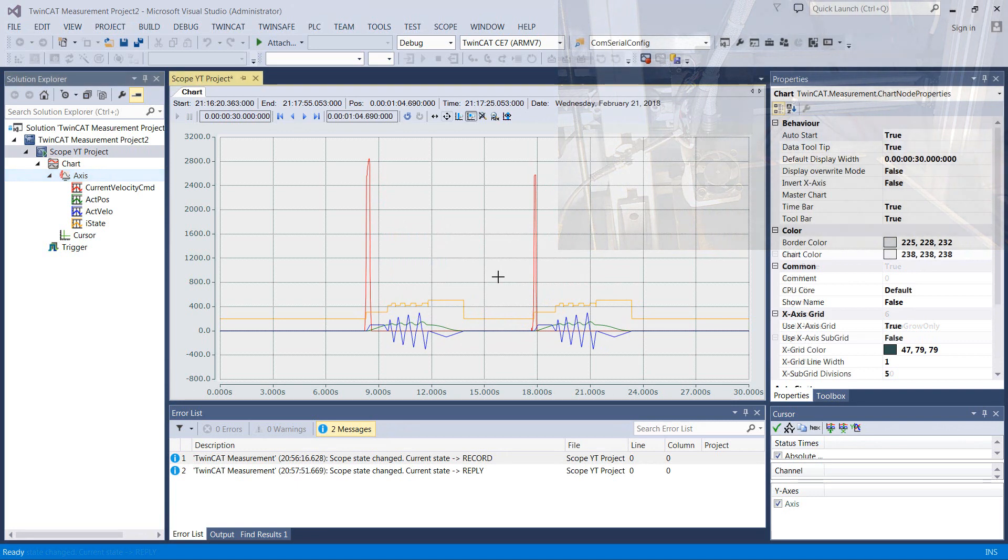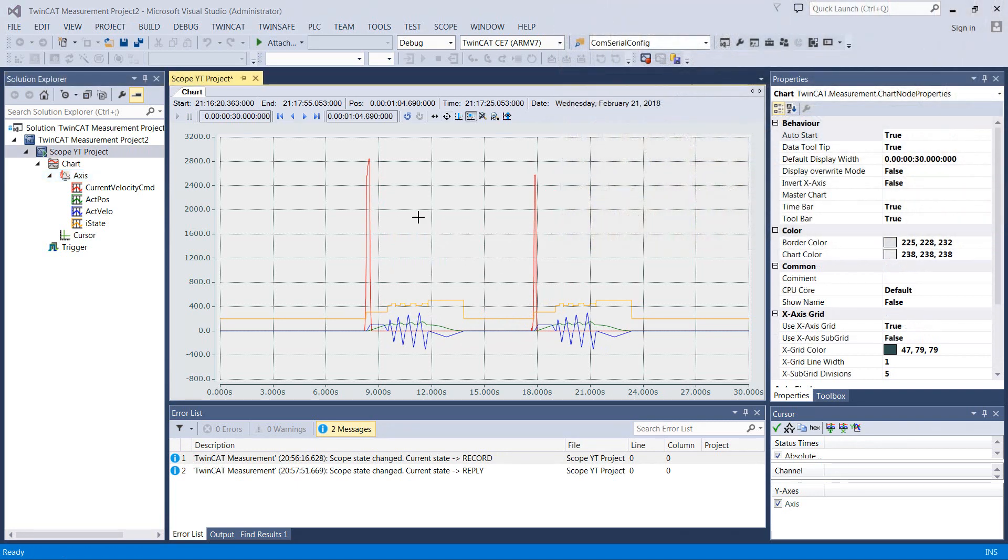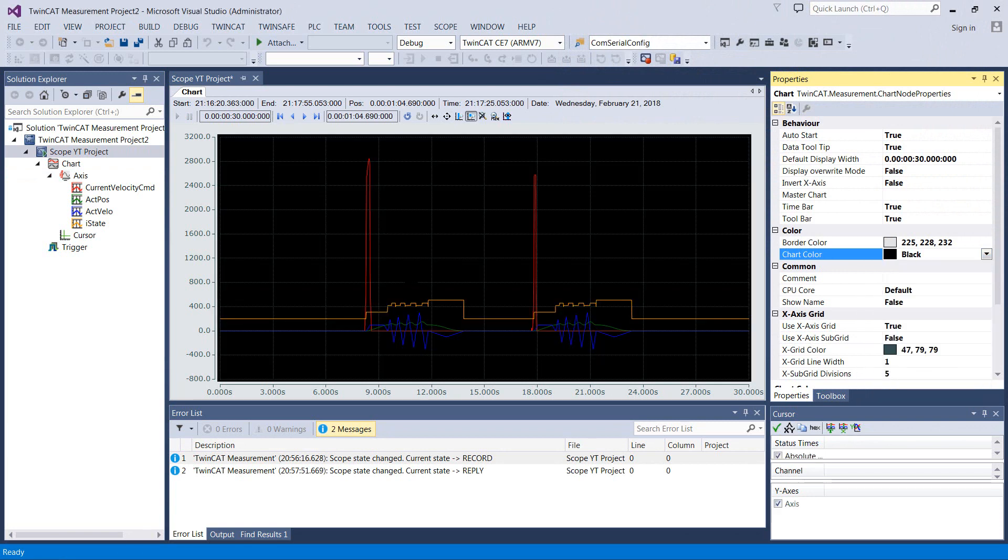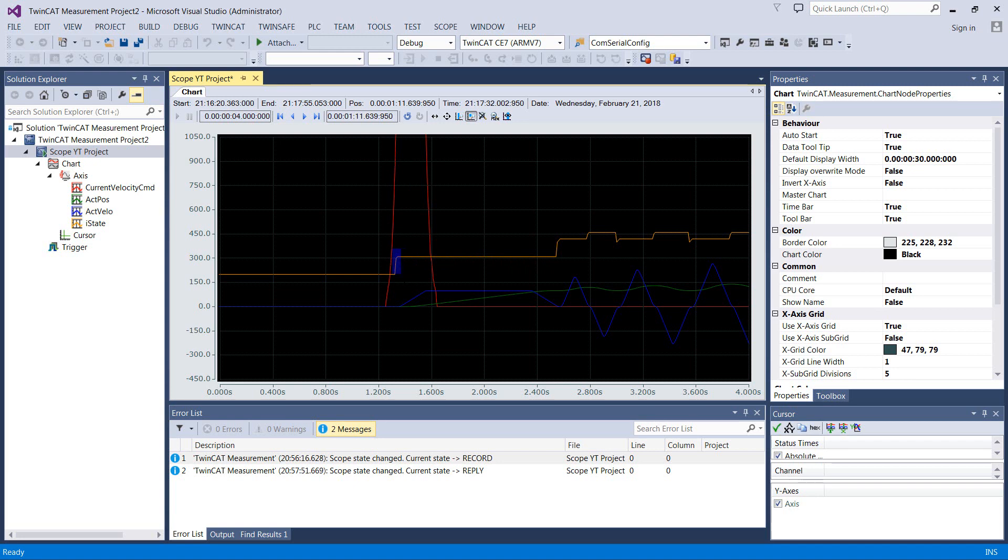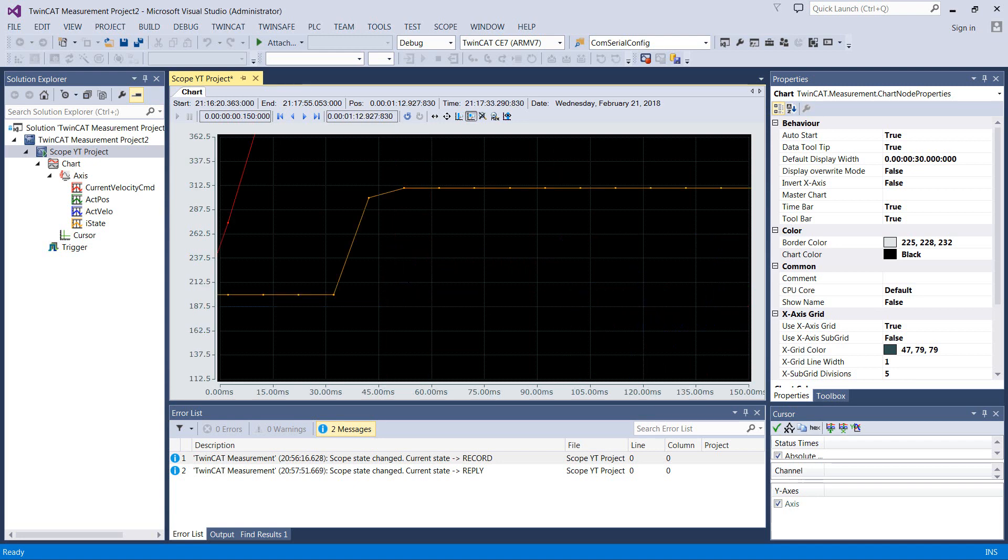All right, so hopefully you can see we've got some decent data here. I'm actually going to turn this chart black because I just like looking at it better that way. So this red line now is where my foot pedal crossed the threshold and started off the state machine. So you can actually zoom in on that and we'll see right as we cross threshold somewhere around here, you can see the state rise up on the very next PLC scan as it moves across here.